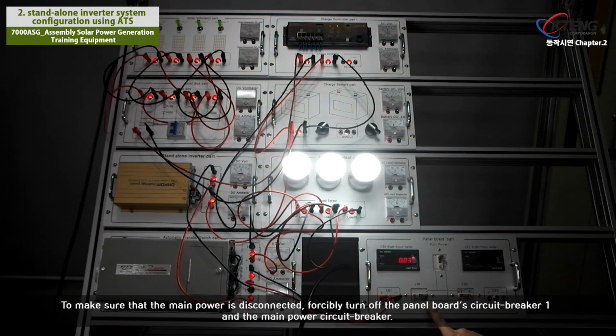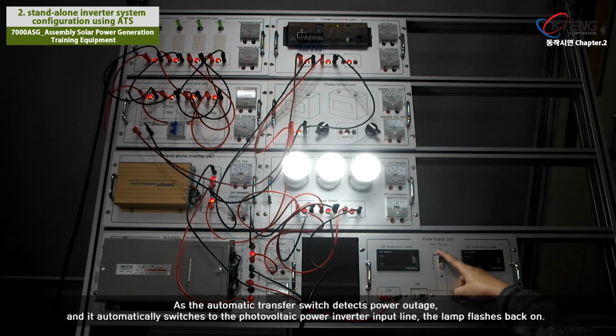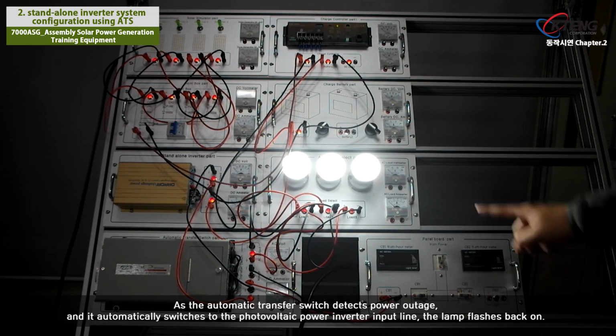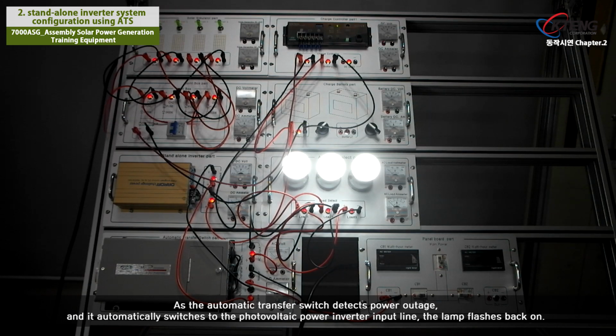To make sure that the main power is disconnected, forcibly turn off the panel board circuit breaker 1 and the main power circuit breaker. As the automatic transfer switch detects power failure, it automatically switches to the photovoltaic power inverter input line, and the lamp flashes back on.